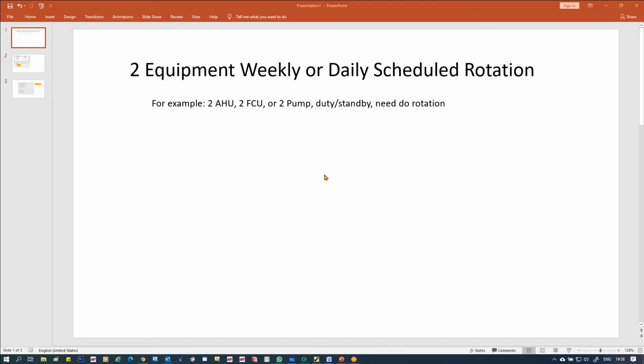Today I show you how to do the weekly or daily schedule rotation programming. For example, if you need to control two AHUs or two fan coils or two pumps, duty and standby, then you need to do a schedule rotation and write the module program.